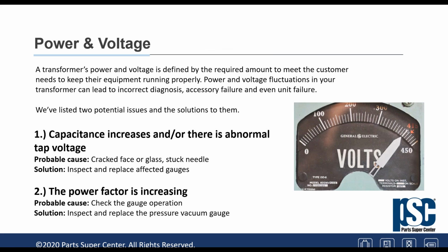Power factor and capacitance increase. Usually these two terms come up when we do a Doble test on the unit. What can make the capacitance of a unit change? Again, a capacitor is nothing more than two electrodes with an insulation in between. That's what's happening in the transformer. If this insulation goes bad because of moisture, deterioration or aging, the capacitance will increase, and we'll learn that on the Doble test. And again, that's typical. Not only will the capacitance increase, but also the power factor.